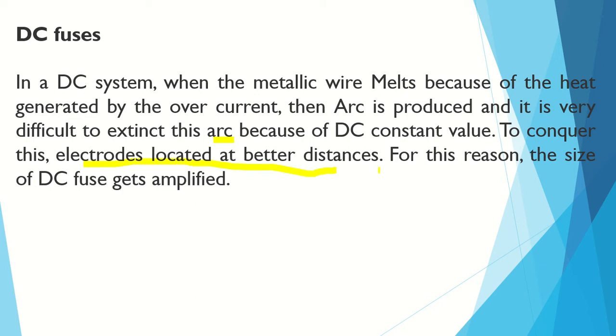For this reason, the size of DC fuse is larger or amplified. Okay, this is the main reason why DC fuses are much bigger in size than AC fuses. Once more, in a DC system, when the metallic wire melts because of heat generated by the overcurrent, that usually happens, right? In order to prevent this overcurrent, we are using fuses. But in a DC system, the arc produced is very high.